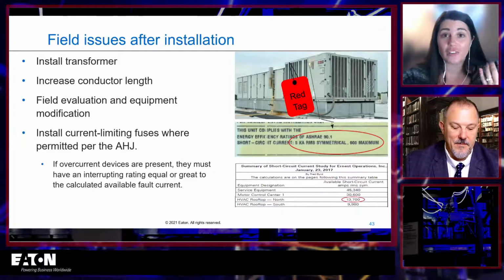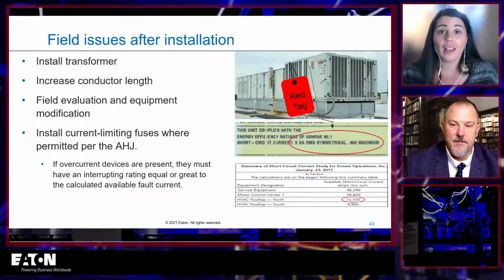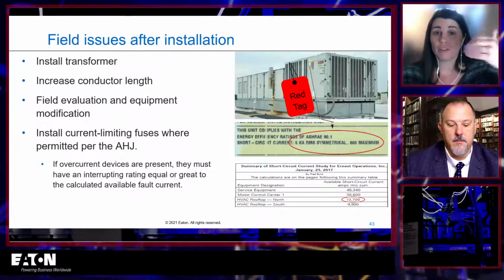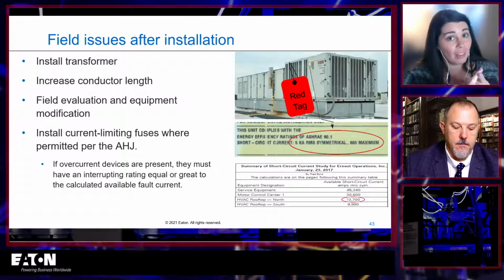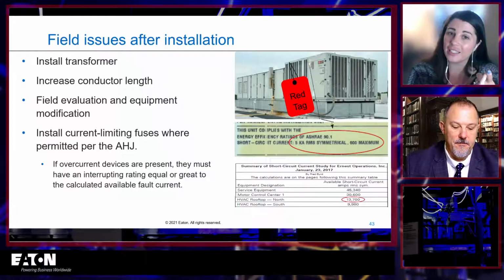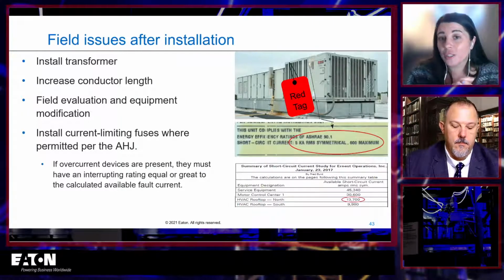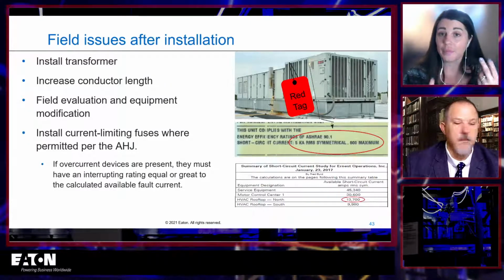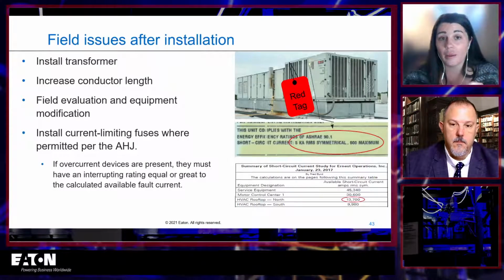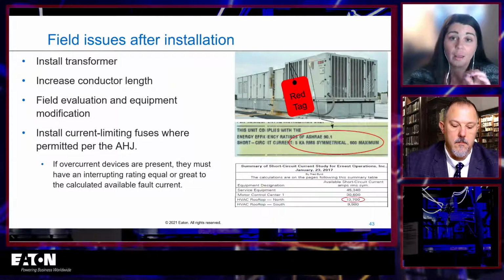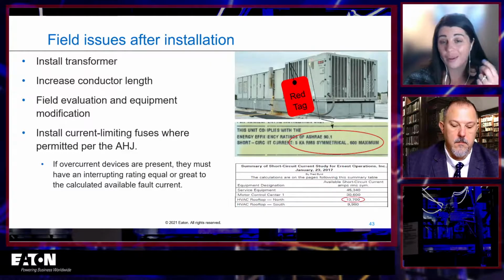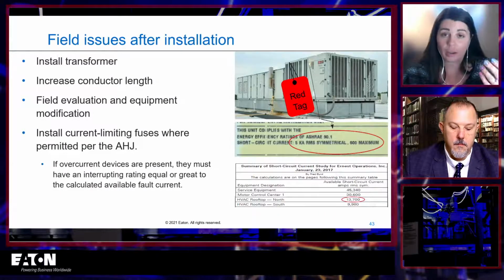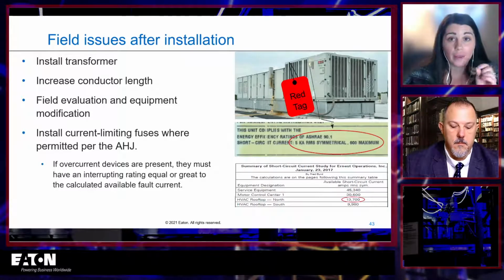We have to use the logic of calculating it as if we were using UL 508A and basically saying now we have this current limiting device in front of it. So whenever we use this, it's important we use peak let-through, right? Because that's what UL 508A tells us to do. And the overcurrent protective device inside that piece of equipment still must be adequate for the available fault current. So those two things you have to do if you're going to try and install a current limiting fuse. And sometimes you can find a good solution using those two, and if you do, it's fine. But a lot of times you wind up having to swap out an overcurrent protective device inside of it anyway, because no matter what, that has to be greater than the available fault current at that piece of equipment.